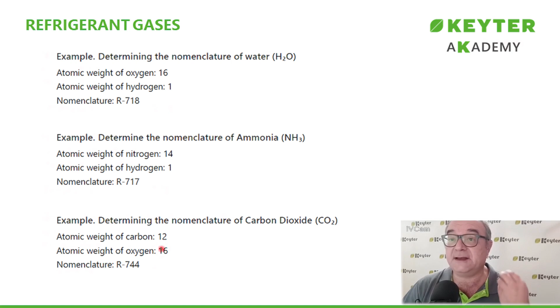Well, we have seen how they are classified. That is, various classifications of refrigerants. We have seen what they are called or how they are named and what those names mean. Let's see other properties tabulated in RSIF in safety regulations for refrigeration installations, which are interesting. Practical limit is the maximum permissible concentration for safety expressed in kg/m3 of refrigerant gas in an inhabited area. It means that if we have a team that is air conditioning a room, that practical limit, apart from other things, would be the first way to see how much refrigerant load the machine can have.